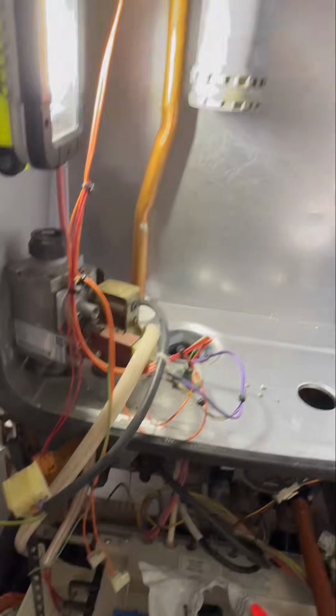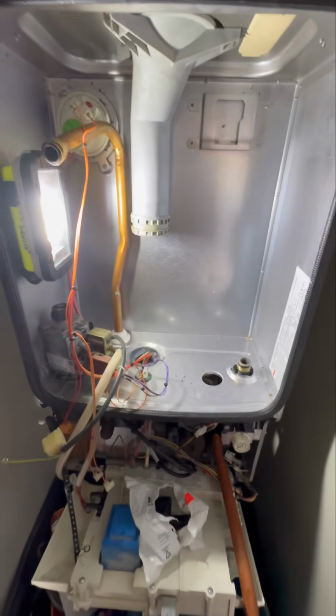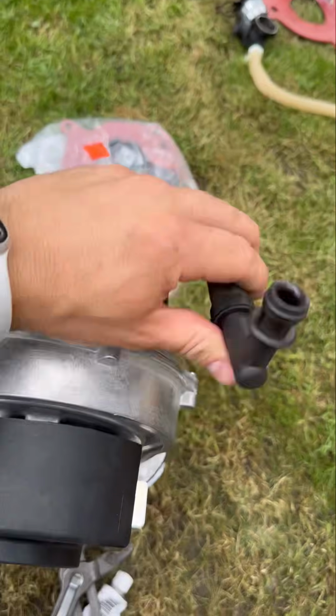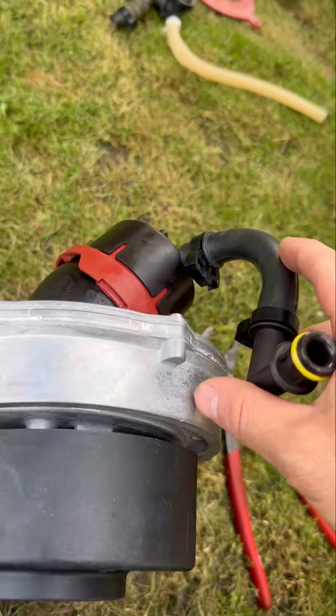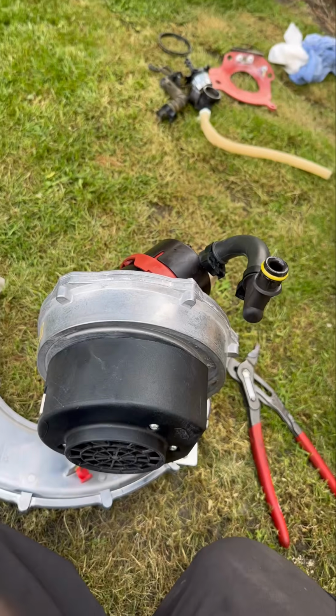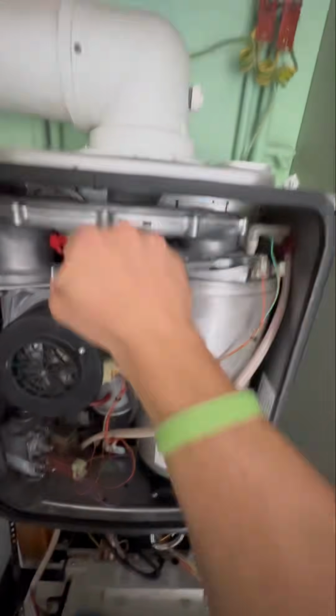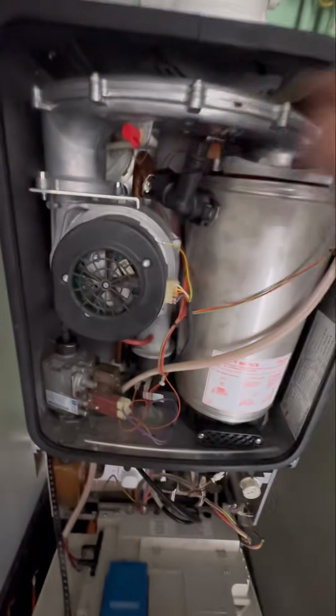Then you're going to look for all the O-rings that you need to change, and washers, and anything else. This doesn't look like it's ever been taken apart, to be honest. It's got the old gas tube on it, so we'll put the new one on, that's better. Also change the electrodes and the fan membrane as well, put all that back together. Oh, and the flow elbow.